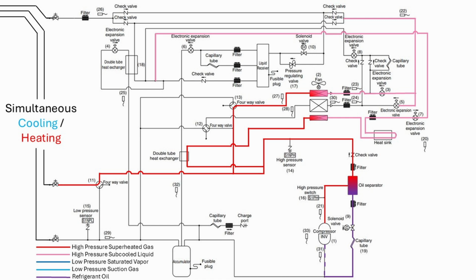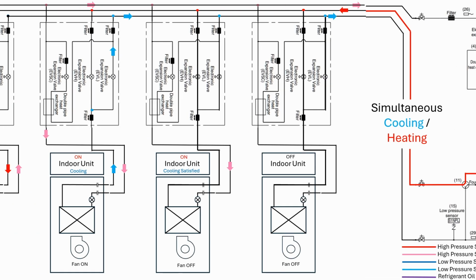The refrigerant from the heat sink will meet up with the refrigerant leaving the liquid receiver. The liquid refrigerant from the upper section of coil will travel through a series of check valves to be routed to the liquid receiver. The liquid refrigerant will be taken off the bottom of the receiver and will be sent to meet up with the liquid refrigerant coming back from the indoor units. The high-pressure saturated vapor will leave the outdoor unit on the high-pressure line and be routed to the indoor units that are calling for heating.